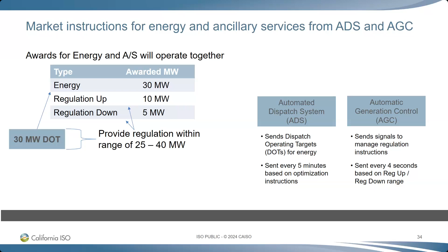So we talked about this last time, but just wanted to make sure we're clarifying - in order to provide ancillary services, if you've been certified as a resource, you need to be able to ramp on and off of the AGC to the dispatch operating point in a linear fashion. You need to be able to stay on AGC for the entire duration of that award, and also have the manual controls to place on AGC. I think that goes back to what you were asking about, Kathleen - it's just more of an awareness of being able to actually manually do this.